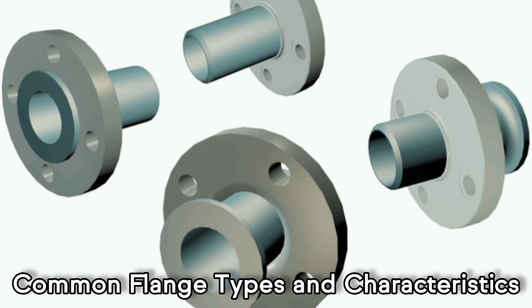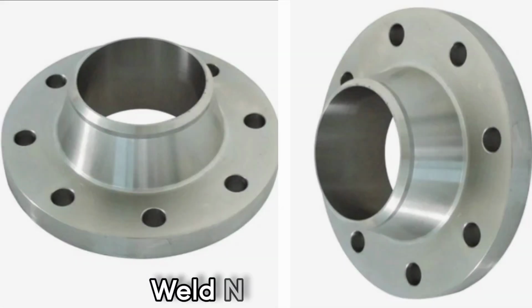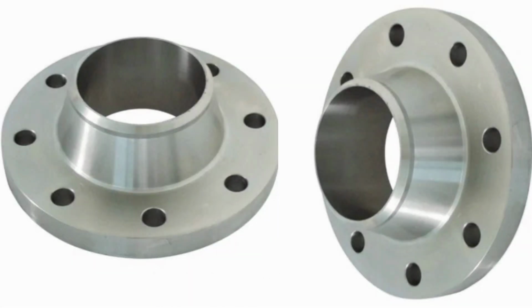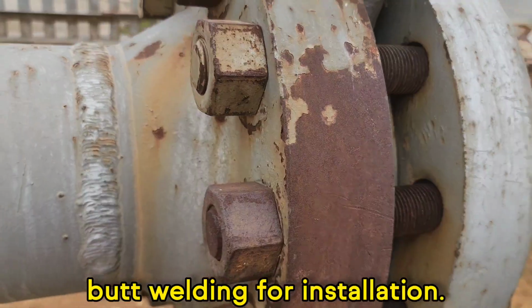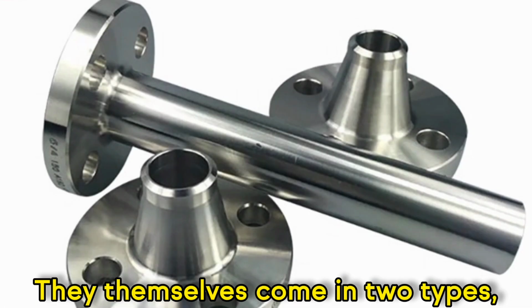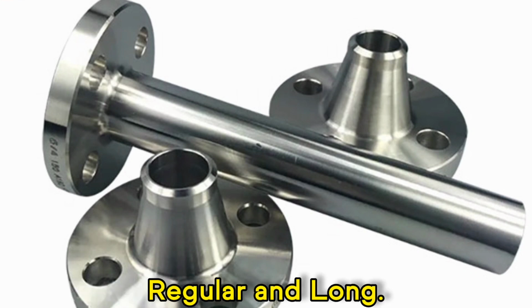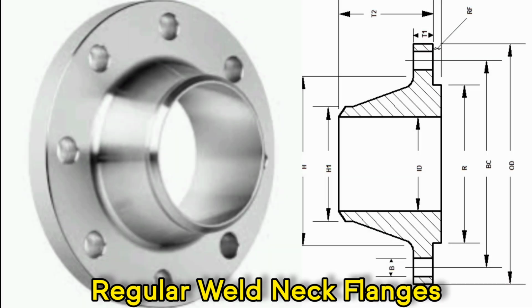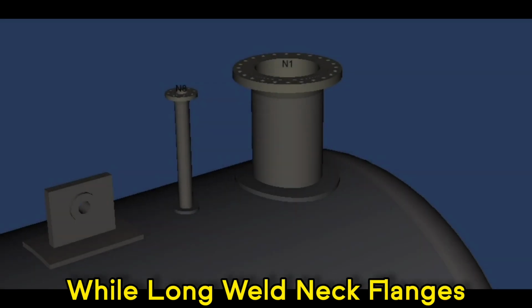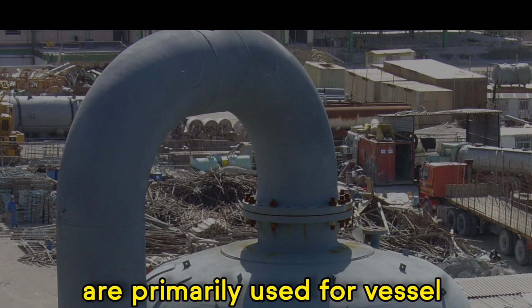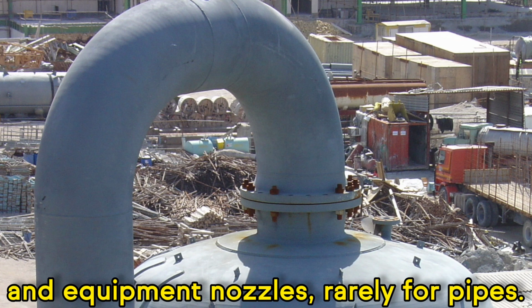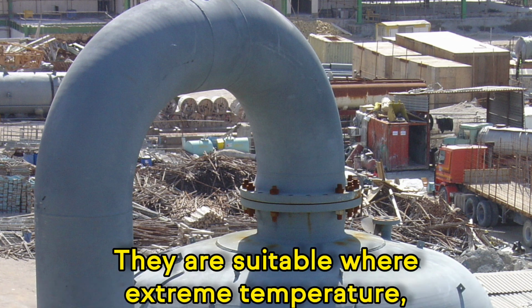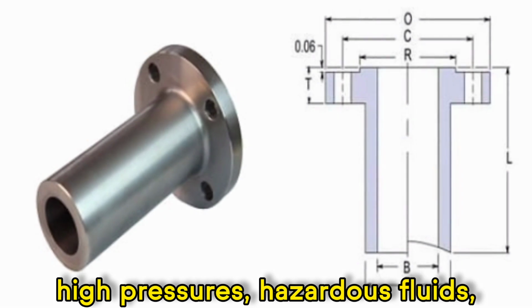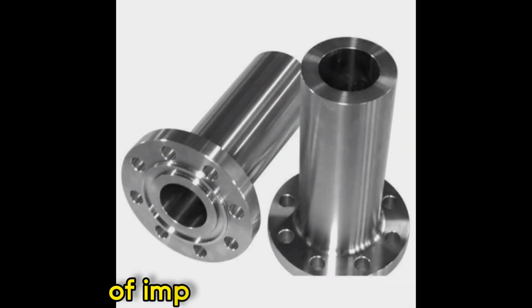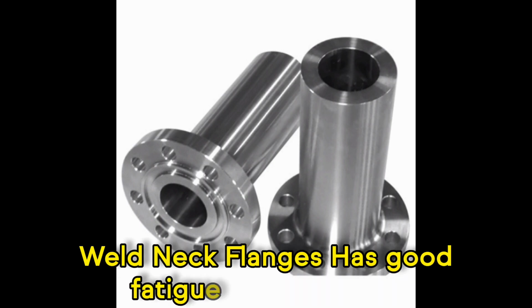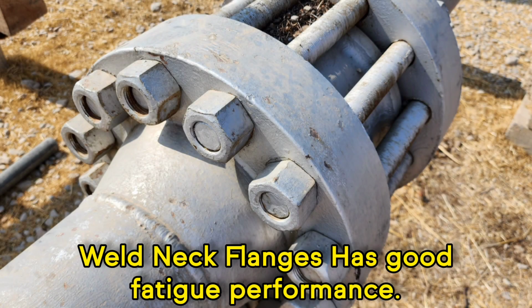Common flange types and characteristics. Number 1. Weld neck flange. Weld neck flanges require welding for installation. They come in two types: regular and long. Regular weld neck flanges are used with welding fittings, while long weld neck flanges are primarily used for vessel and equipment nozzles, rarely for pipes. They are suitable where there are extreme temperatures, high pressures, hazardous fluids, shear deformations, and applied stress of impact and vibrations. Weld neck flanges have good fatigue performance.